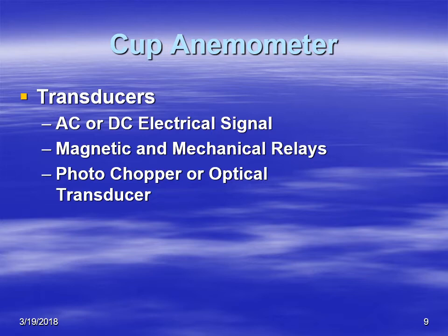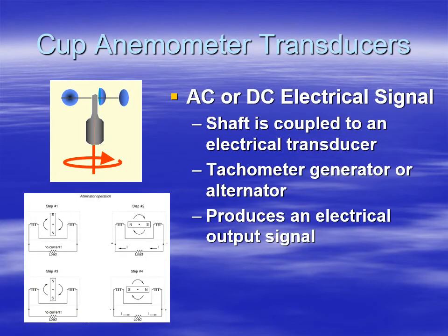The types of transducers that are used for cup anemometers are either an AC or DC alternator/generator, magnetic and mechanical relays, or photochopper or optical transducers. So let's take a look at the first one, the AC and DC generators, the signals. An AC or DC electrical signal is generated by the cup anemometer through its shaft. The shaft is attached to the cup wheel. The cup wheel is rotating. At the end of that shaft, there's a magnet. The magnet is rotating through an electric field, which generates a current. And that's what we can measure.